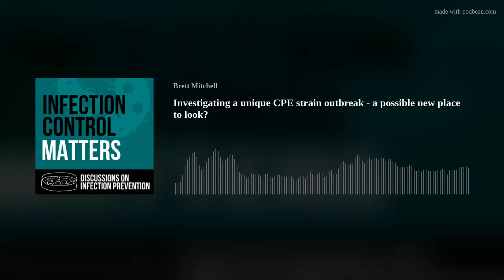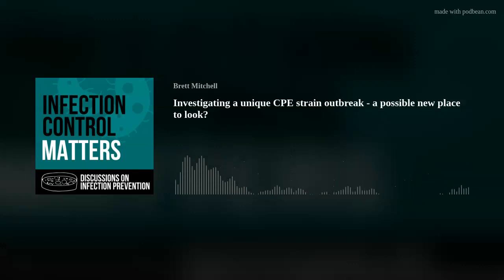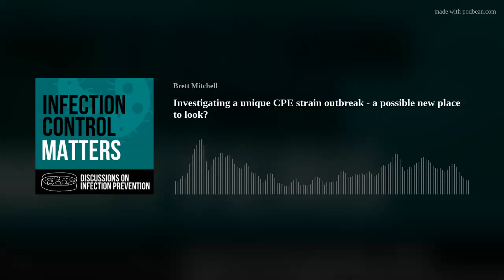And I think it's difficult to rationalise exactly. You may not understand the contamination that you've got as well. And have you spoken to any of the manufacturers about this? Because with respect to them, they might have designed it without thinking we're going to get biofilm in here and potentially spread multi-resistant gram-negatives around. The design may have been tinkered with over the years, but they haven't really been thinking we need to incorporate this into our design. And if they did do that now, it's probably going to be 5 or 6 years before you saw a new machine anyway. Have they said anything to you?